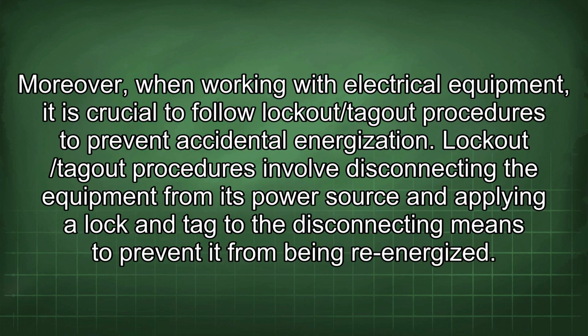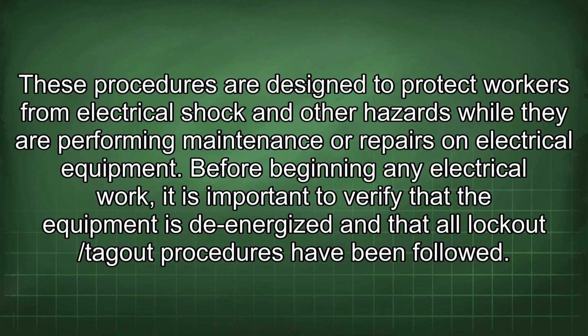Moreover, when working with electrical equipment, it is crucial to follow lockout/tagout procedures to prevent accidental energization. Lockout/tagout procedures involve disconnecting the equipment from its power source and applying a lock and tag to the disconnecting means to prevent it from being re-energized. These procedures are designed to protect workers from electrical shock and other hazards while they are performing maintenance or repairs on electrical equipment. Before beginning any electrical work, it is important to verify that the equipment is de-energized and that all lockout/tagout procedures have been followed.